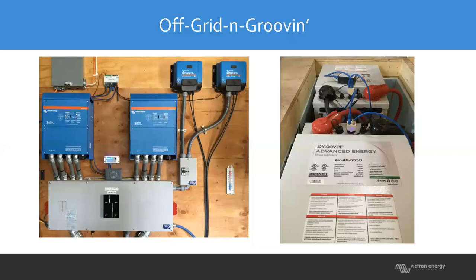In the past, as an installer putting in off-grid systems mainly using lead-acid batteries, there was a great deal of making sure the inverter set points were in line with the battery specifications, to make sure the inverter would disconnect before the battery was permanently damaged.